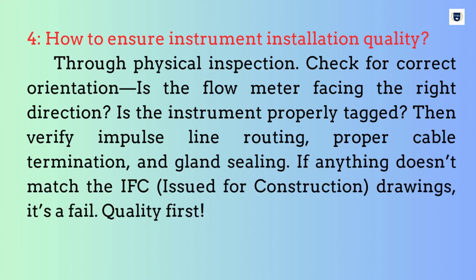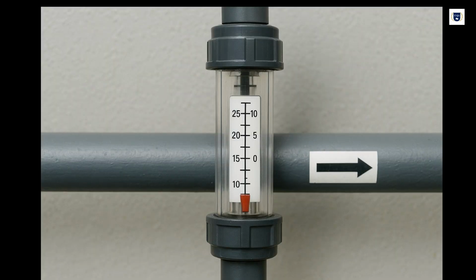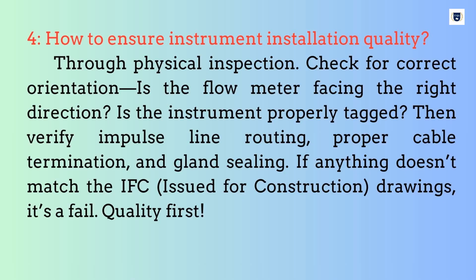How to ensure instrument installation quality? Through physical inspection. Check for correct orientation. Is the flow meter facing the right direction? Is the instrument properly tagged? Then verify impulse line routing, proper cable termination, and gland sealing. If anything doesn't match the IFC, issued for construction drawings, it's a fail. Quality first.